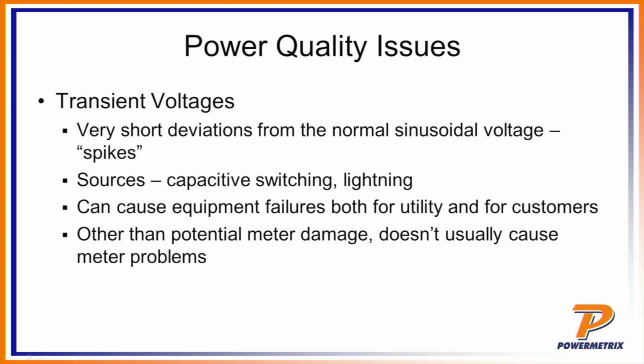Those protection devices, of course, do have a lifetime, and so if you live out in the Midwest, say, where you have a lot of lightning, it may be required that you change your meters out a little bit more often than not. But the meter itself is designed to ride through that, and as such, it shouldn't really be a problem in terms of the accuracy of the meter. Like I said, it may cause more damage, but it really won't cause a problem in terms of the accuracy of the meter. Another example of transient voltage will also be capacitive switching.